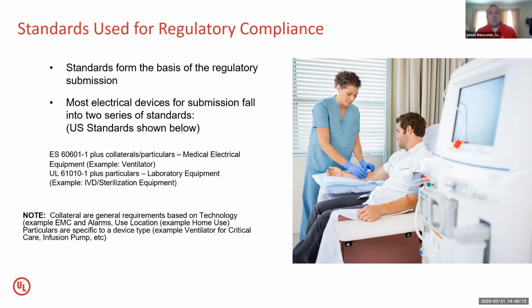So when we're talking about ventilators, for example, the 601 series of standards actually has 3 different categories of ventilators, whether they be critical care, that's one type, or where they go into the next step and they go into the home use ventilators that may, depending upon the level of breathing that the patient needs, fall into 2 other buckets.